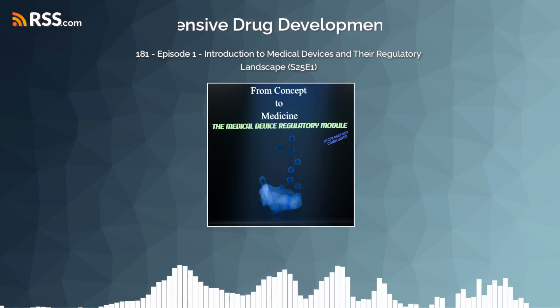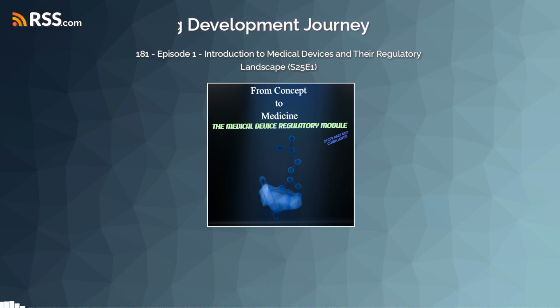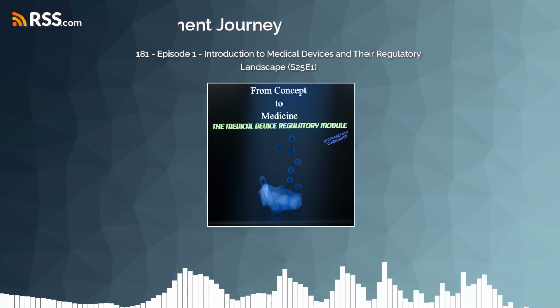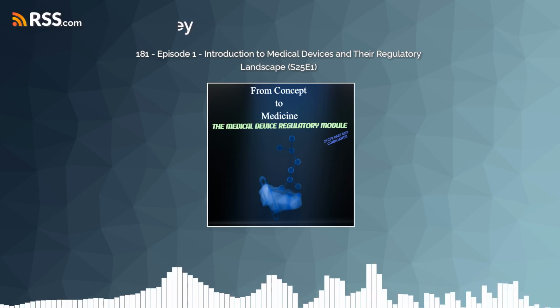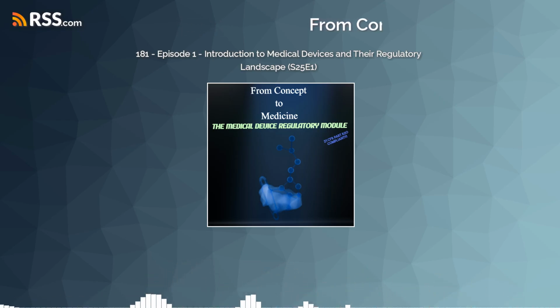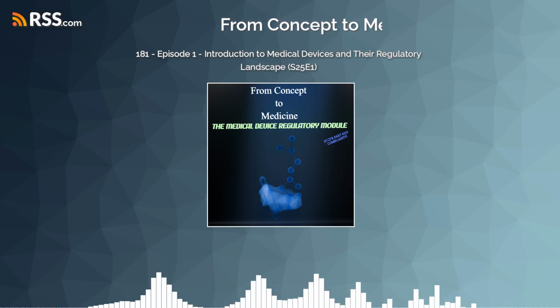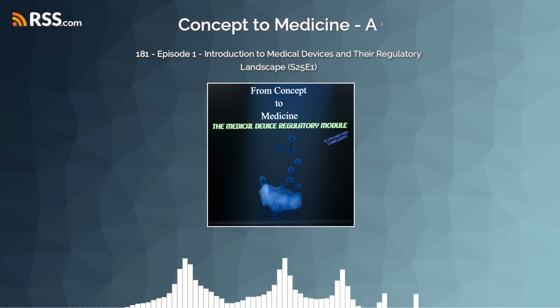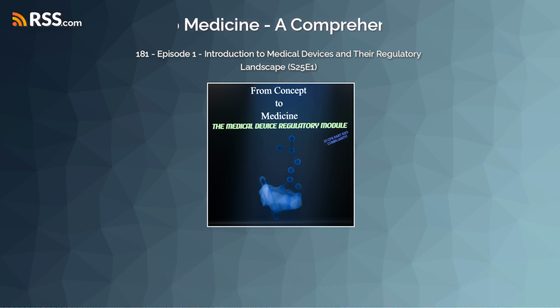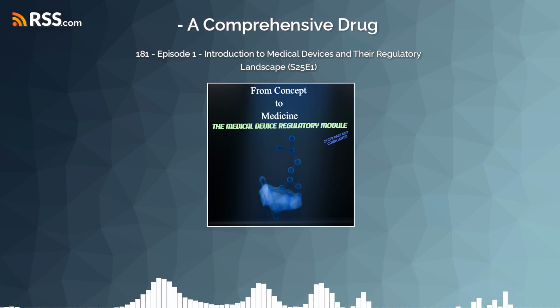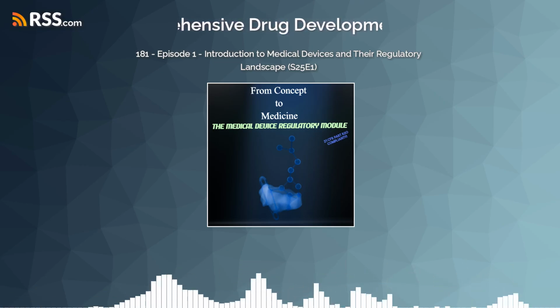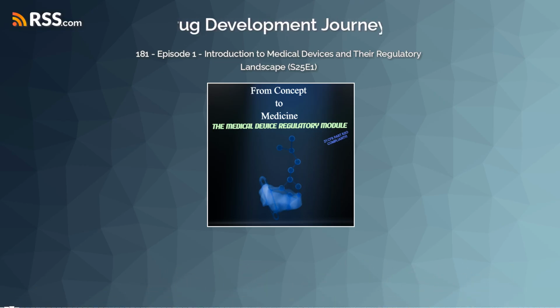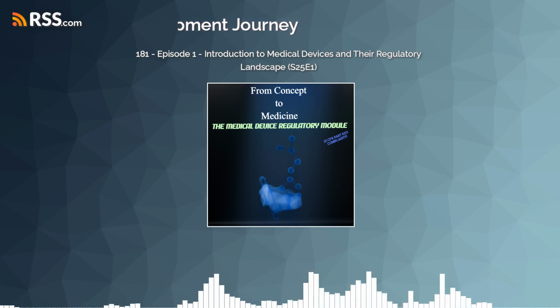This is a critical part of the QMS post-market activities. Manufacturers must have robust procedures for identifying, investigating, and dealing with non-conforming products, whether caught internally or reported from the field. Crucially, they need solid systems for handling complaints. Complaints aren't just problems, they're valuable feedback that can identify potential quality issues or emerging risks. The investigation has to be thorough and documented.